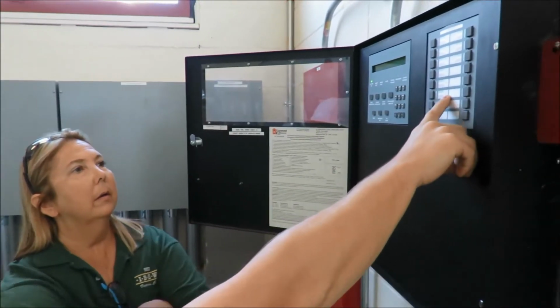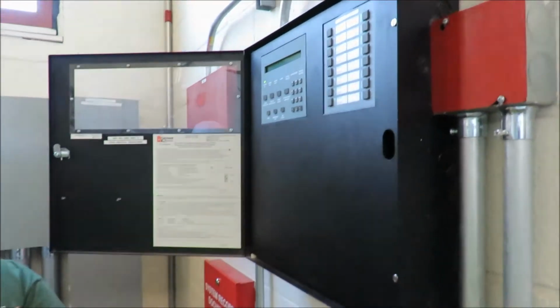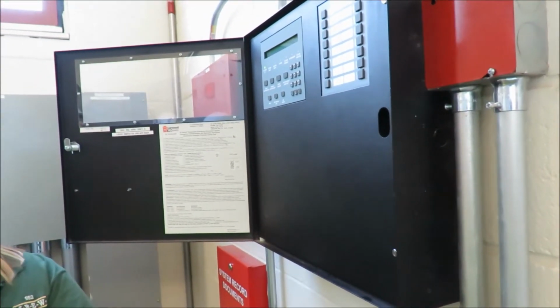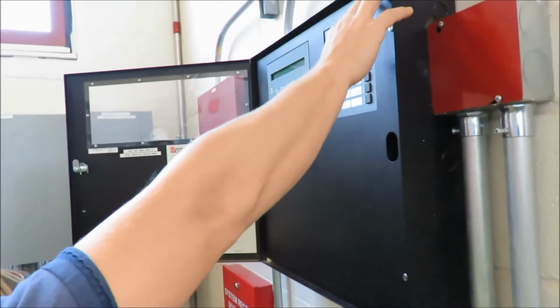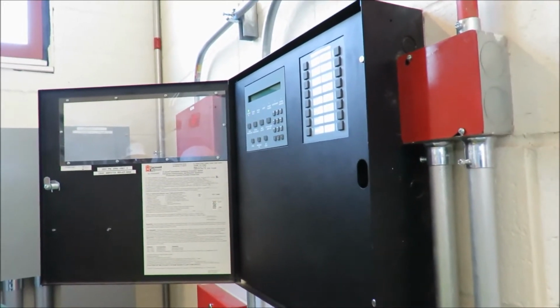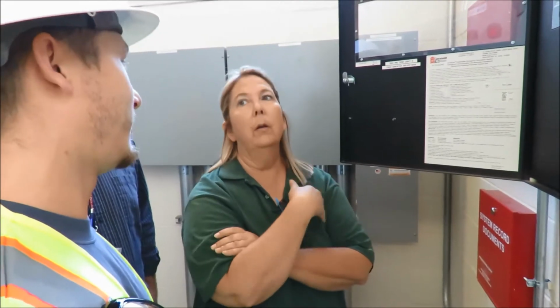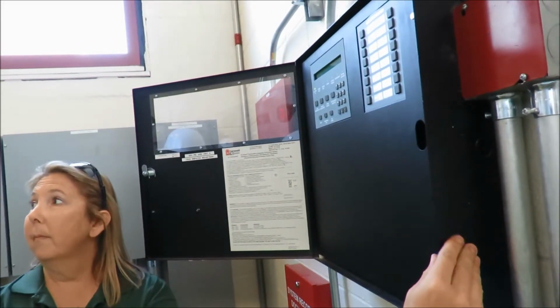However, on here, you also have your bypasses. So we have the NAC bypass, no audio visual, elevator bypass. So testing wise, we can bypass the elevator, and people can still use it. Air handler bypass, dampers bypass. There's tons of dampers out here, so we want to make sure, you're going to fry your air handler if you don't bypass the dampers as well. Or if we do the dampers and then don't do that. Could the engineers come over and bypass that if they're doing any testing?